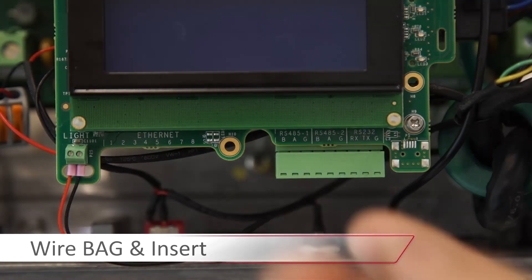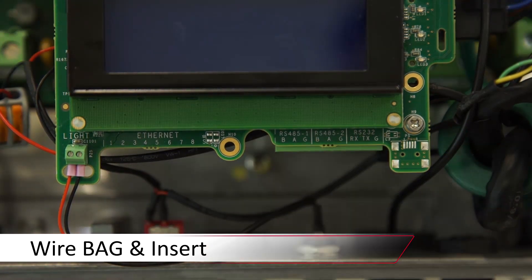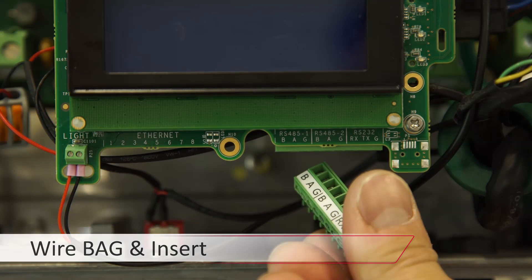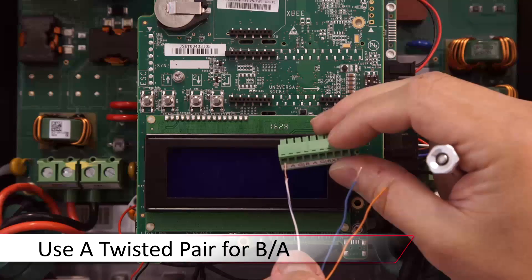Remove the RS-485 termination block from the communication board. Today we're going to be using CAT5 for our wiring, so we'll isolate one twisted pair and a third conductor of any color. We chose white-blue and blue for B and A, and orange for G.